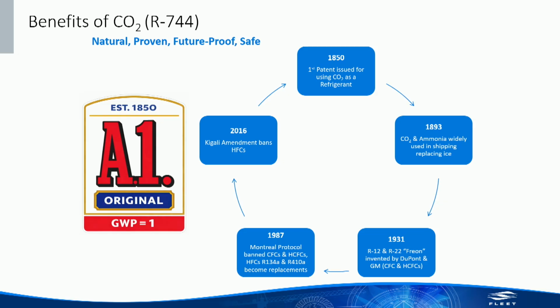So that kind of forces us back toward natural refrigerants, CO2 being one of them. I know there's a lot of talk about propane being another, but obviously there are flammability issues there. The beauty with CO2 is it's still an A1—it's been around a long time, it's proven, and it's actually the baseline for what GWP is, so it has a GWP of 1. There are very few refrigerants out there, if any, that can actually beat it with respect to global warming.